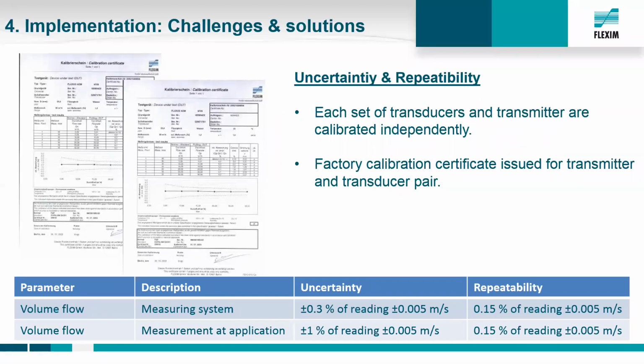0.3%. So considering the uncertainty in the field, we have to take also into account other uncertainties, for example, of the application, like the pipe roughness, the circumferences, the composition of the pipe material, and then we have to state an uncertainty of the measurement at the application, and then we state 1%. So considering all these tolerances of circumferences or unknown wall thicknesses, composition of pipe material tolerances. So for sure, if we had a perfectly known application, we could state also the measuring system uncertainty of 0.3%, but in real life, we always have some tolerances in the application parameters.